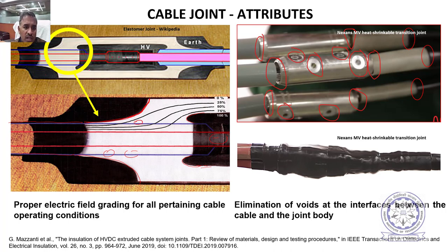So this is how, then again above the conductors, this is actually jointing of the conductor portion. Above the conductor, you see this semicon layer will be a cylindrical structure. Again, this one will be laid over the conductors. So this kind of structure provides a certain radius of curvature by which the electric field is limited again. So this is the typical structure of a joint.